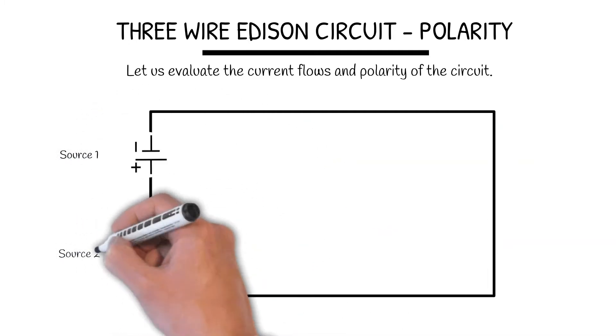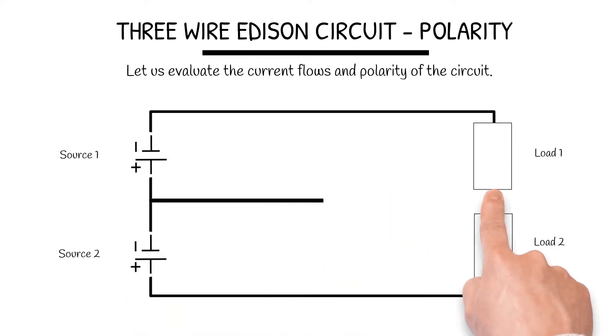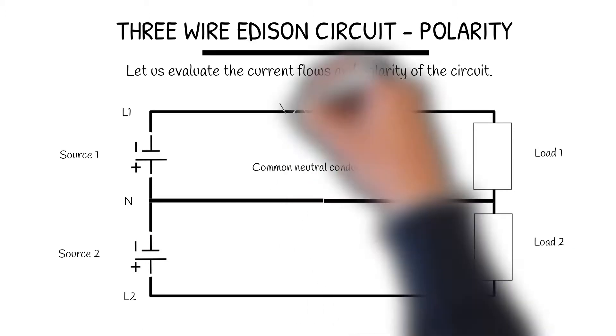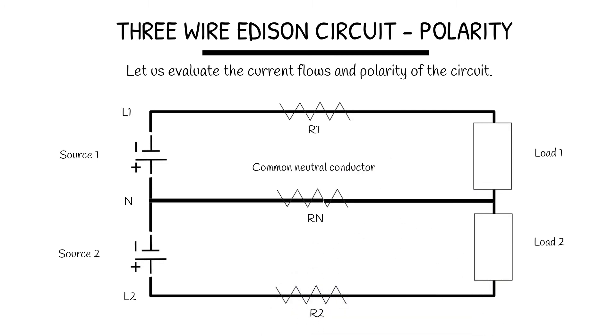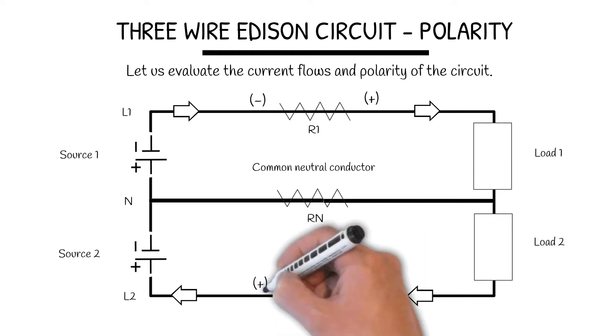3-Wire Edison Circuit Polarity. Let us evaluate the current flows and polarity of the circuit. Here we have the common neutral conductor. Because of electron flow, current leaves the negative terminal, which creates a negative and positive on the top resistor. On the bottom, current is going into the source, which gives a negative on one side and positive on the other.